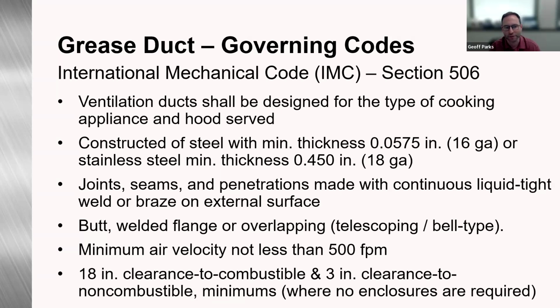Also covered in the IMC are the joints, seams, and penetrations, made with a continuous liquid-tight weld or braze on the external surface. The types of connections are butt weld, welded flange, or overlapping, the telescoping or bell type. It defines minimum air velocity to be not less than 500 feet per minute for the systems. 18-inch clearance to combustibles, 3-inch clearance to non-combustibles. And these are minimums where no enclosures are required.